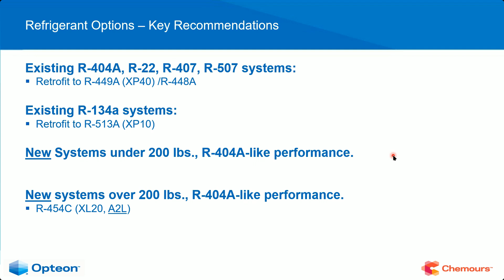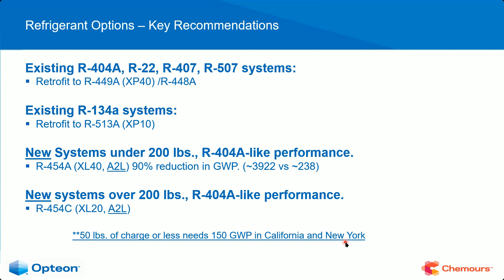Now, new systems under 200 pounds with 404A-like performance will be 454A, a 90% reduction in GWP - that's 3,922 versus 238, a big deal. New systems over 200 pounds, we're going with 454C or XL20 Opteon, both A2L refrigerants - that's a big reduction. I noted here that 50 pounds of charge or less needs to be 150 GWP in California and New York at this time, when this is being recorded.